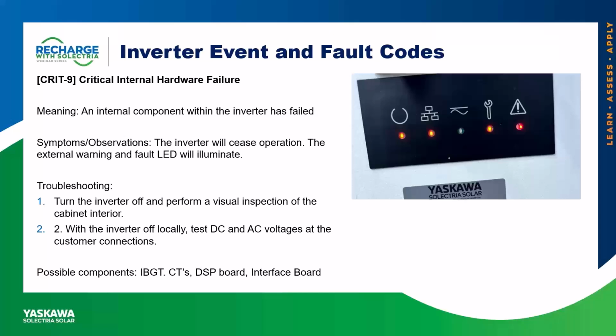In terms of troubleshooting, you would want to start by turning the inverter off and performing a visual inspection of the cabinet interior to verify nothing has obviously been broken. With the inverter off locally, we would then recommend you test DC and AC voltages at the customer connections. Now at the bottom, I list possible components that could be in question when Crit 9 results, those being the IGBTs, the CTs, the DSP board, the interface board, or the power supply. If the technician calling us is trained, we can have them perform a static internal check on the IGBTs using the documentation they receive upon completion of the course, but we can resend said documentation if need be.